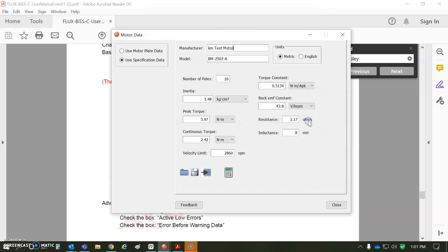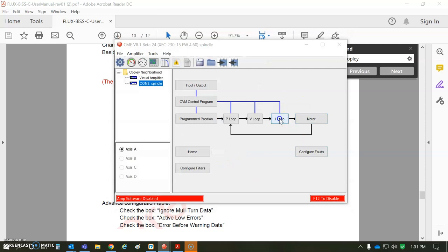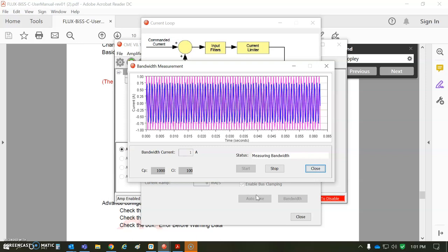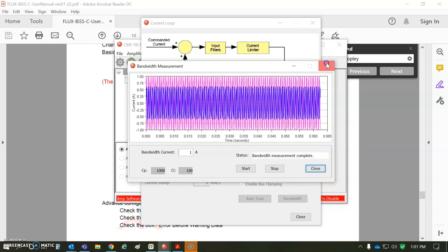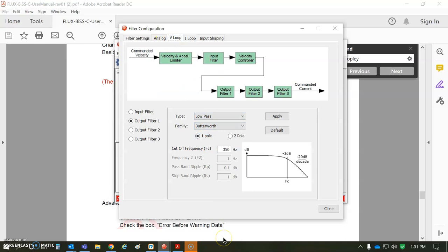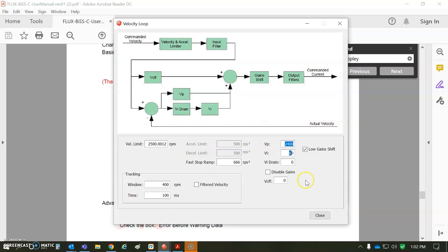Here's the data for the motor. You can't go too fast. Current loops are all tuned up. Gets about a kilohertz of current loop bandwidth. This is a direct drive motor, so maybe a little bit more bandwidth. Yeah, one kilohertz is fine. The velocity loop is all tuned up for stiffness. I moved the pole out. There's no load here yet. If you had a large inertia compared to the motor inertia, you might dial this down to 100. You may have to lower the VP and VI again. That's maybe twice as much for less bandwidth. But right now, drive lots of move and settle. That's pretty cool.